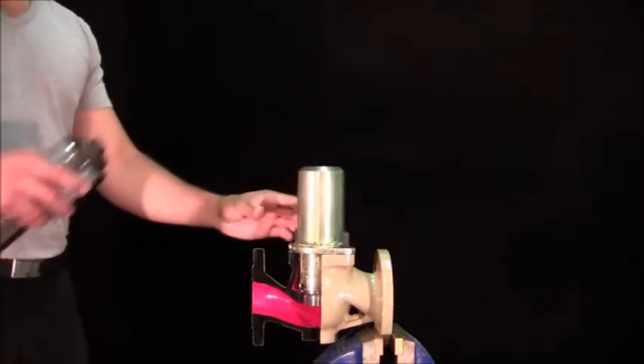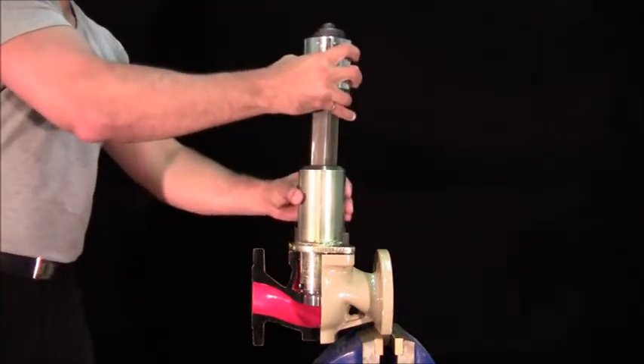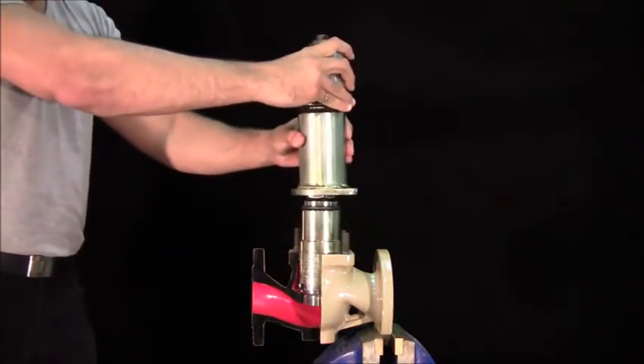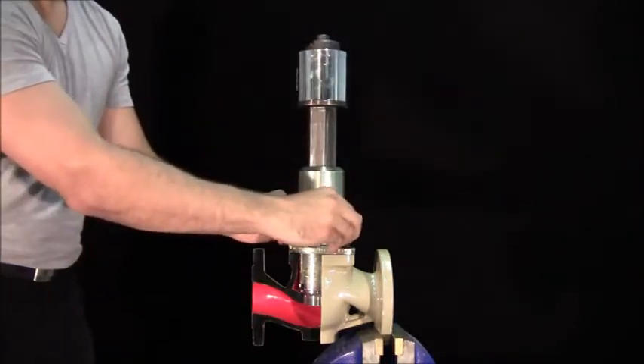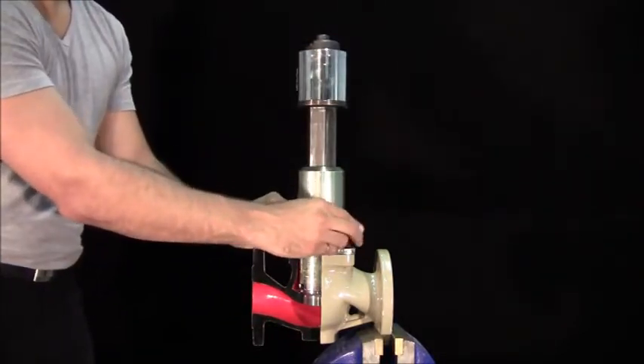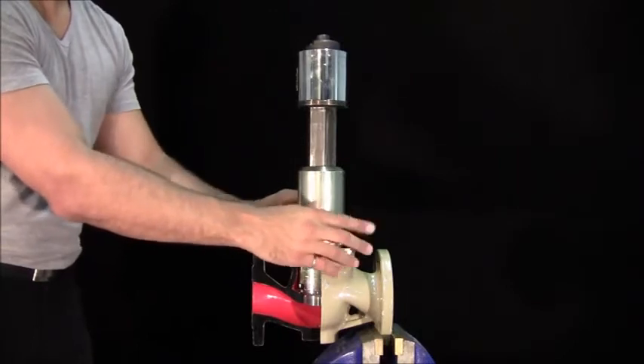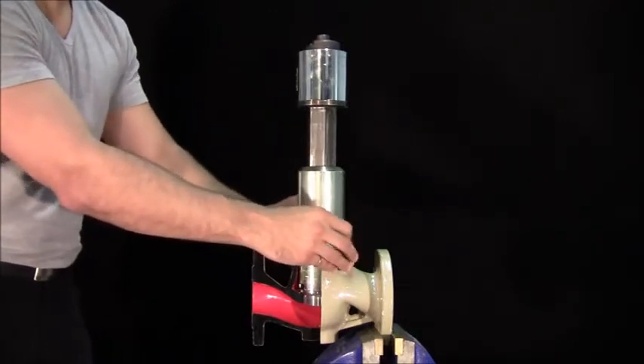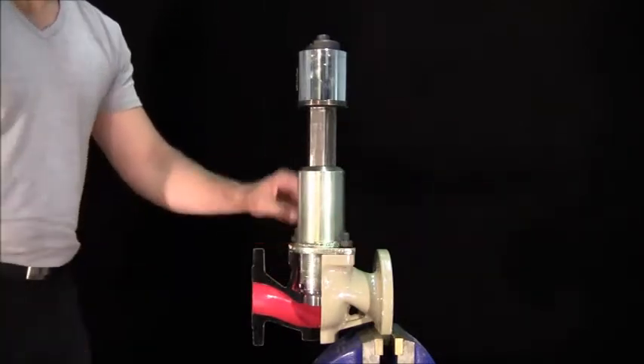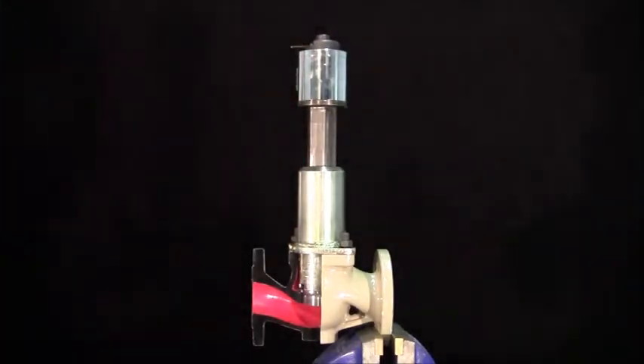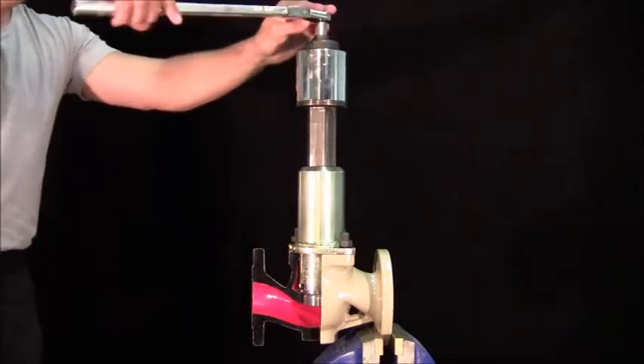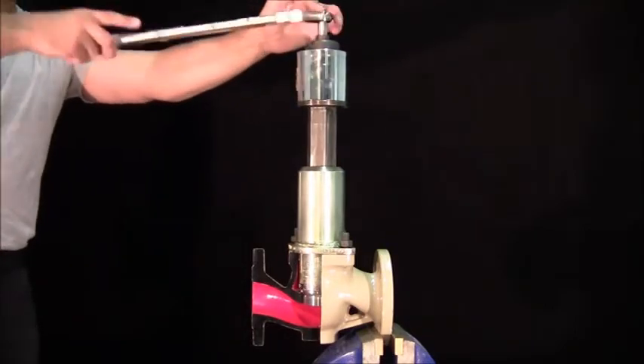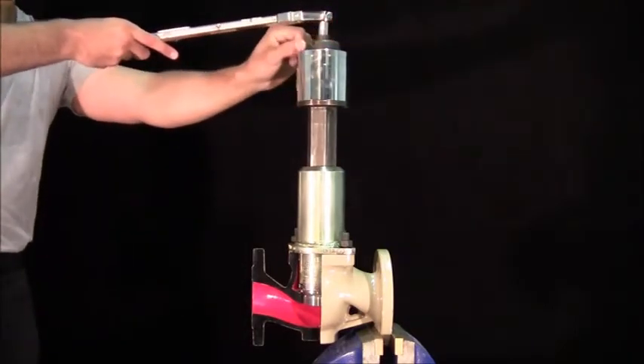Now, the seat tool, support flange and torque multiplier can be used to tighten the seat to the required torque specification. Install two nuts to hold the tools firmly to the valve body before using a torque wrench. The seat is now installed.